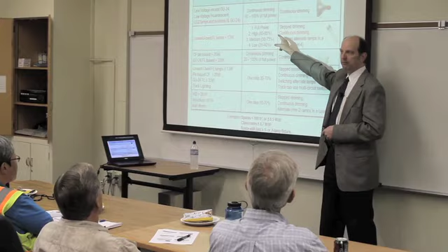Compared to right now, what percentage of your buildings have got dimming lighting in them? I mean, you've got the conference rooms maybe. That's about it, right? Now all these other spaces are going to have to be dimmable, which means the wiring is going to be more complex, which means the contractors who install it are going to have to spend more time making sure that they really understand how the wire goes in. It means it's going to be a different ballast than you're using before. All this comes into play because California really wants to get the enabling technology of dimming into all these spaces, and now we can take advantage of all these other things that we might want to do.